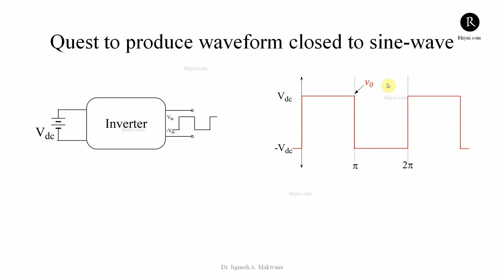Let's understand what happens if the output voltage waveform or output current waveform is not pure sine in nature, because our major equipment is built to operate on a sine wave with a frequency of 60 or 50 Hz depending upon the region. An impure sine wave of voltage or current results in increased heating in equipment and conductors, due to higher hysteresis and eddy current losses in transformers and motors, or misfiring in variable speed drives. It will also affect the performance of power electronics drives, and cause torque pulsation in motors.